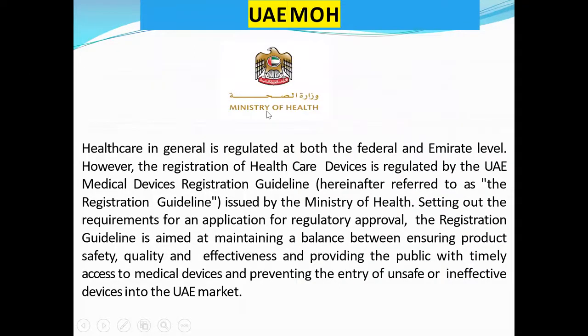Then UAE. Again, it is one of the Ministries of Health which is popular in the GCC. Here healthcare in general is regulated at both the federal and emirate level. So, United Arab Emirates, and that is why it is regulated by both the federal and the emirate level. However, the registration of healthcare devices is regulated by the UAE Medical Device Registration Guideline, herein referred to as the registration guideline, issued by the Ministry of Health, setting out the requirements for an application for regulatory approval. The registration guideline is aimed at maintaining a balance between ensuring product safety, quality, and effectiveness, and providing the public with timely access to medical devices and preventing the entry of unsafe or ineffective devices into the market.